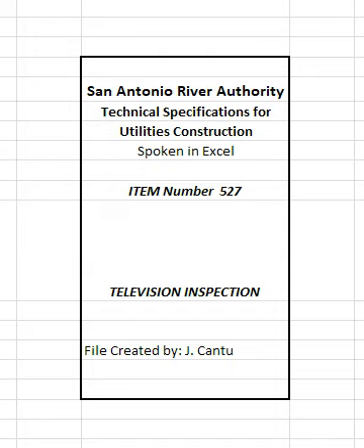Under no circumstances shall the flow be interrupted or stopped, such that damage is done to either private or public property, or sewage flows or overflows into a storm sewer or natural waterway. The contractor shall provide bypass pumping of sewage around each segment of pipe that is to be televised and shall be responsible for all required bulkheads, pumps, equipment, piping, and other related appurtenances to accomplish the sequence of pumping. A qualified person shall man the pumps, on site, at all times during the bypassing procedure.